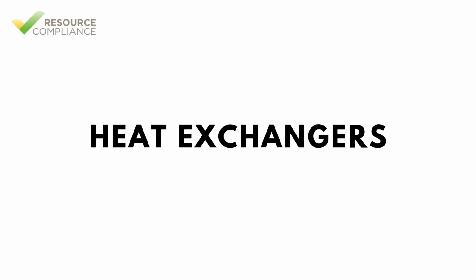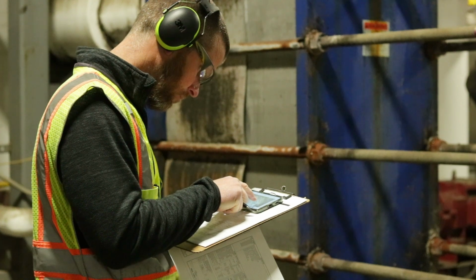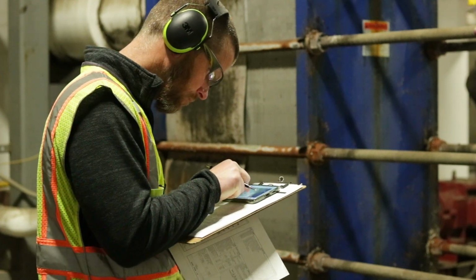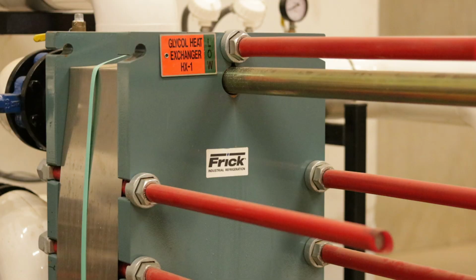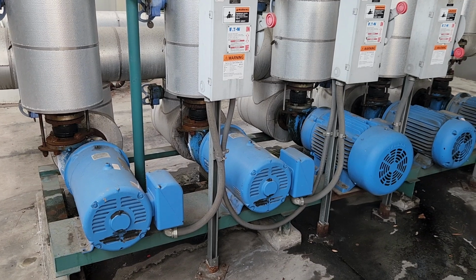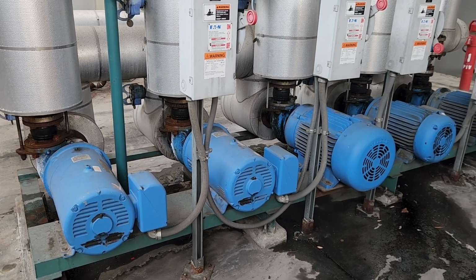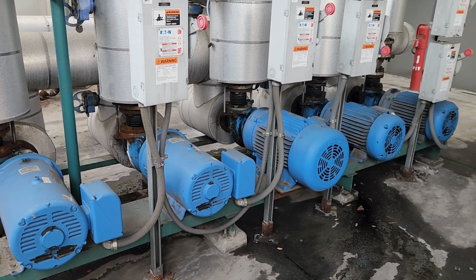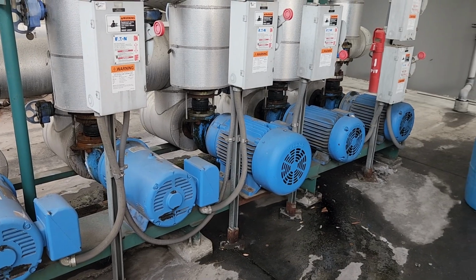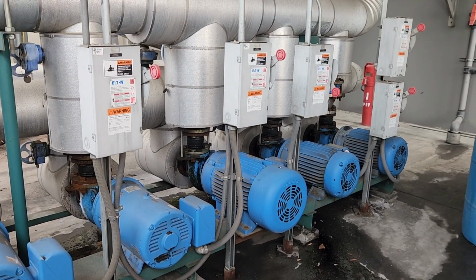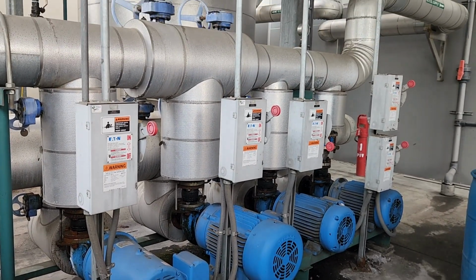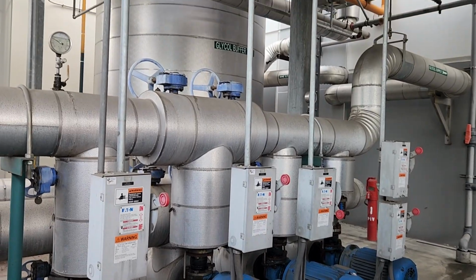Heat exchangers used to cool a fluid are started similarly to an air cooling evaporator, except instead of having fans, these units will typically have one or more pumps that need to be activated to start heat transfer. The control valves associated with heat exchangers are similar to those of air cooling evaporators. Heat exchangers are usually started and stopped from a PLC HMI or a dedicated control panel.